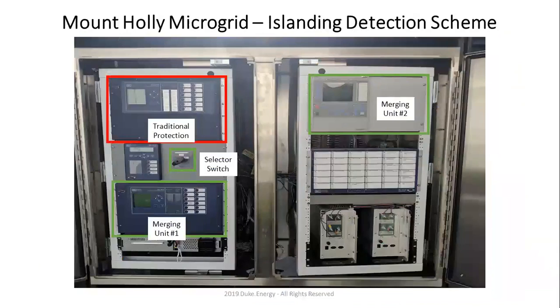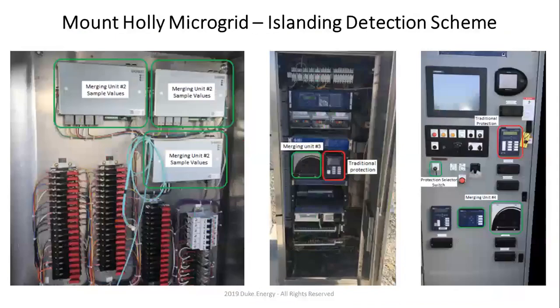So how does this look? What you see here is the internal enclosure that protects the four-way switchgear. You have traditional protection on the left, the relay. Then on the bottom you have merging unit 1 that's tied to way 1 and way 2 of the four-way switchgear, and on the right side you have merging unit 2. Now when you have a merging unit, remember you have your CTs, your PTs, and your digital inputs and digital outputs, right? So these are merging units 1 and 2, and these are the CT and PT parts. Some merging units are built to take CTs, PTs, as well as digital inputs and outputs. Some of them have these separated.